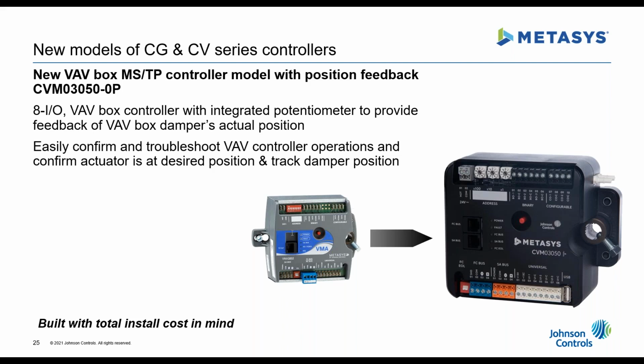So there is a potentiometer now in the actuator model that gives you true feedback on the position of the damper actuator, which is great, especially for customers that are out there that want to take advantage of a true feedback. Before we were relying on a command position, and that reliance was making the command at 50%, and we didn't have really any feedback. A lot of times that damper wasn't actually positioning itself at 50%.